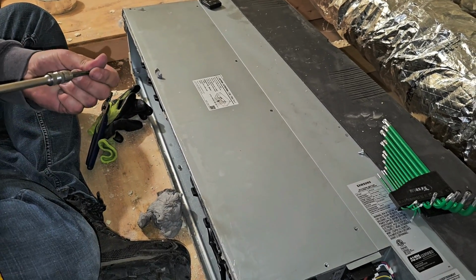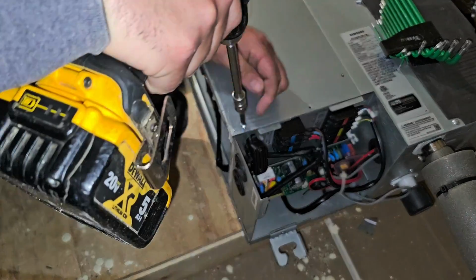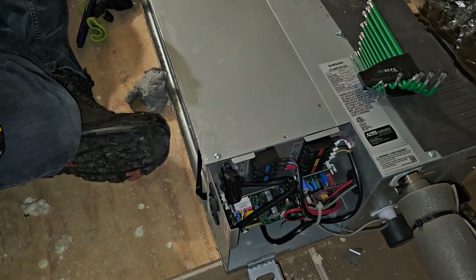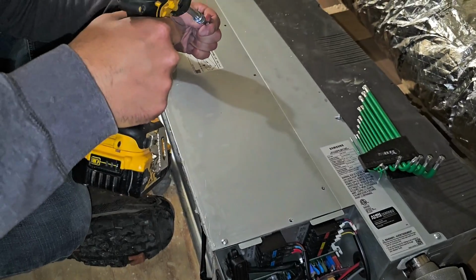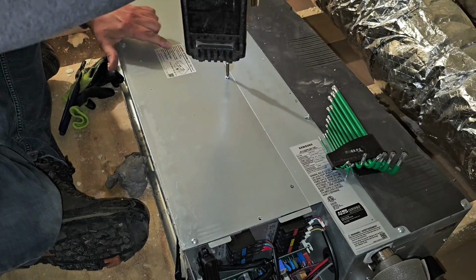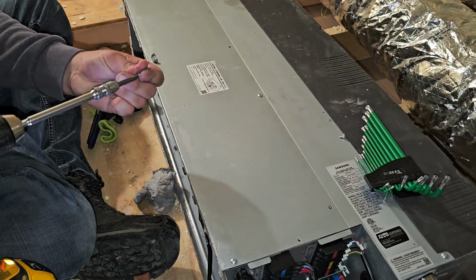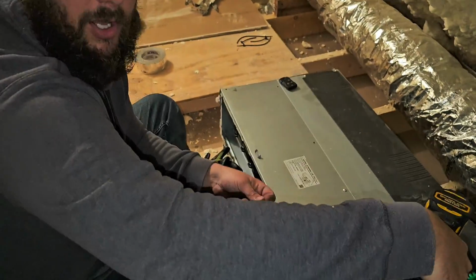We're almost ready to put this back together. I'll go ahead, and while Nick and James are putting the duct connections back together, I'll go ahead and pump the system full of nitrogen, do the pressure test, then vacuum, and then we will open the valves back up.